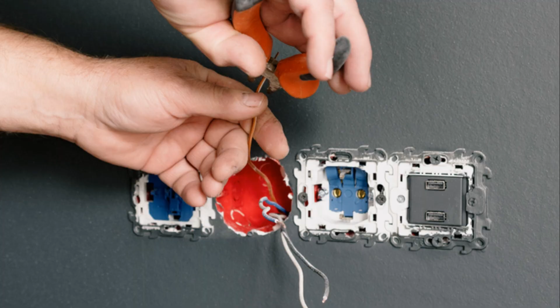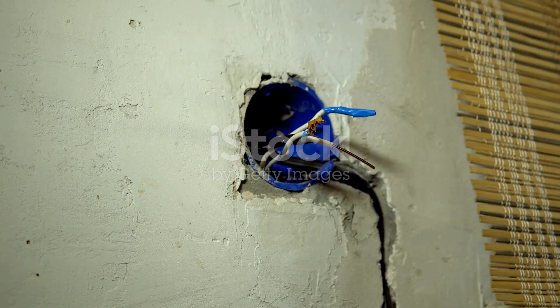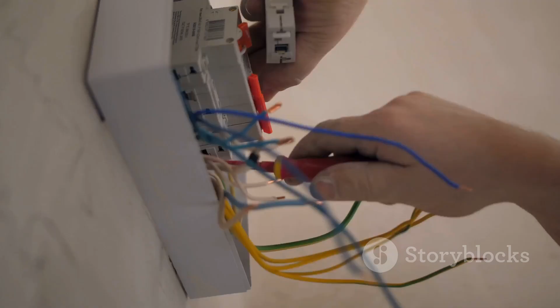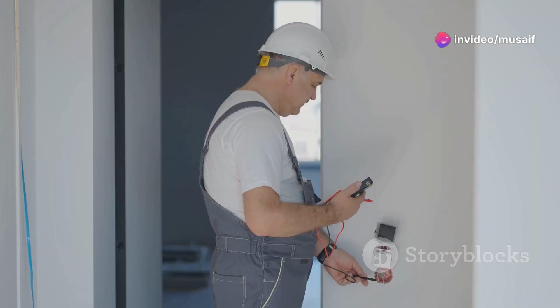Let's be honest, water and electricity don't mix. That's why it's crucial to have ground fault circuit interrupter, GFCI, outlets in areas where water is present, like kitchens, bathrooms, and laundry rooms. These outlets are specially designed to detect even the slightest imbalance in electrical current. If a ground fault is detected, the GFCI outlet will trip and cut off the power in a fraction of a second, preventing a potentially fatal shock. It's a good idea to test these outlets monthly by pressing the test button. If the outlet doesn't trip, it's a sign that it's not working properly and needs to be replaced. Don't take any chances with electrical safety, especially around water.